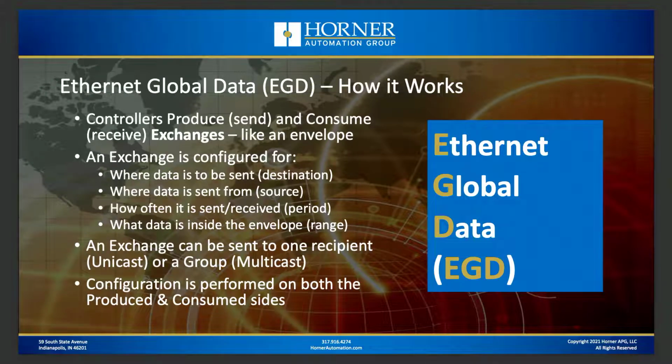Okay, let's talk about how it works. EGD is based around the fact that controllers are going to produce and consume what are called exchanges. And you can think of those like an envelope. An exchange needs to be configured with where data is to be sent, you know, what's its destination, where the data is going to be sent from, okay, what's the source of the data, how often is the data going to be sent.